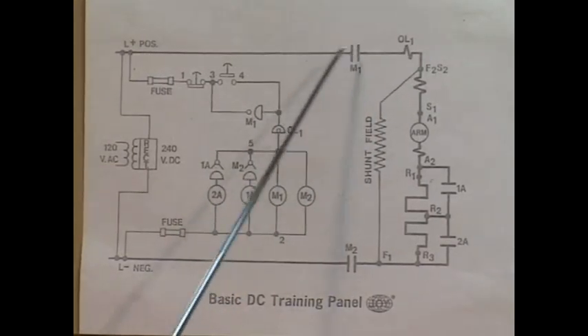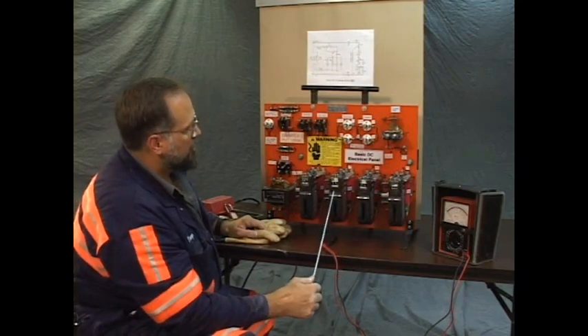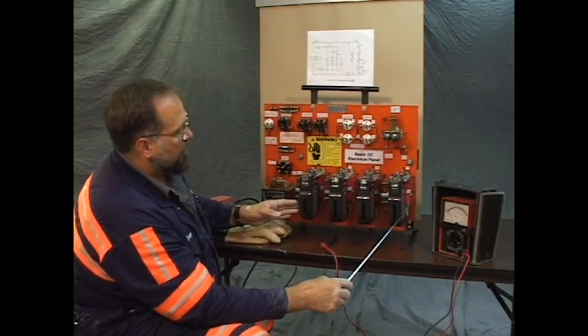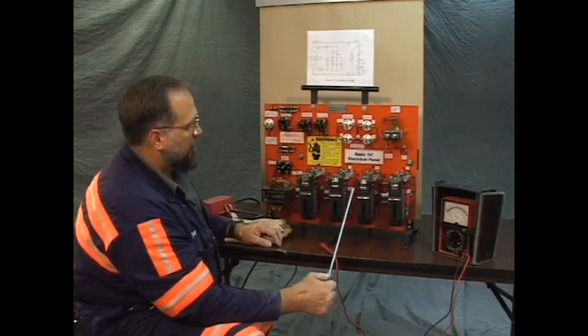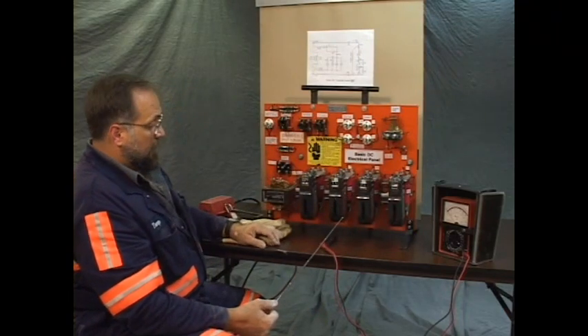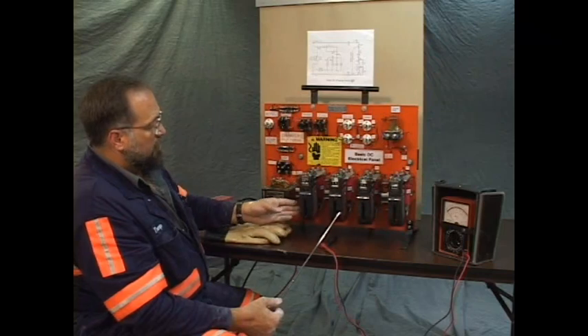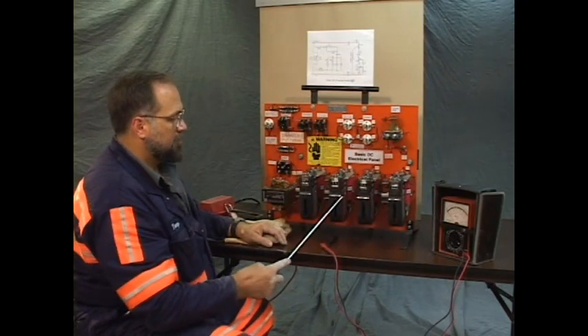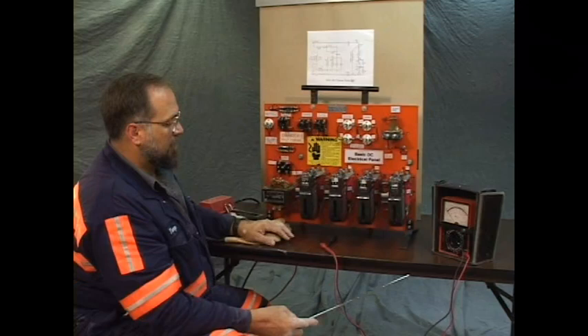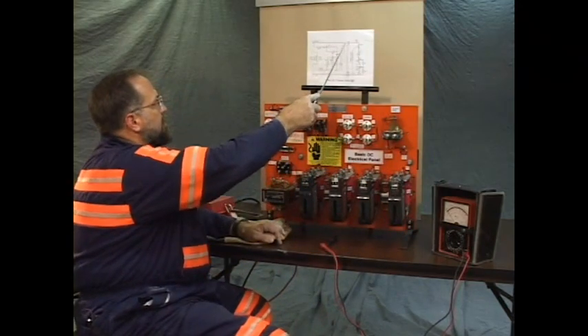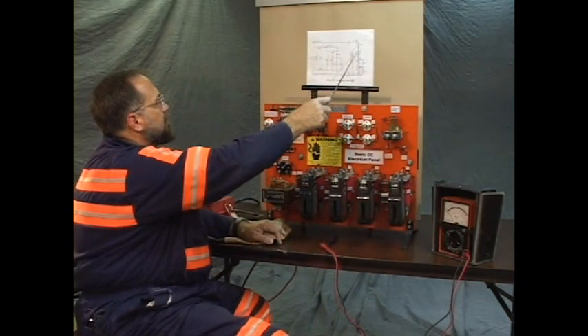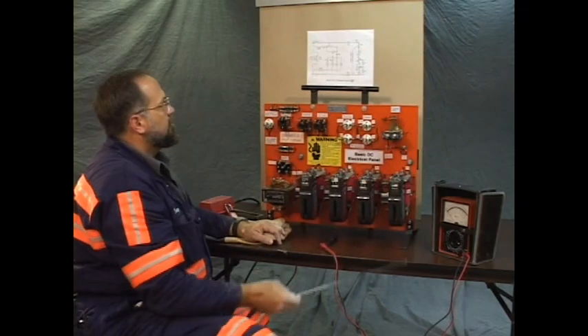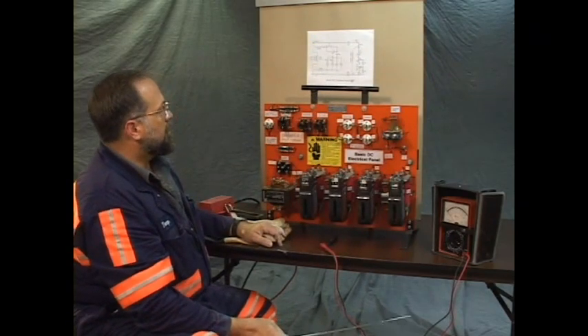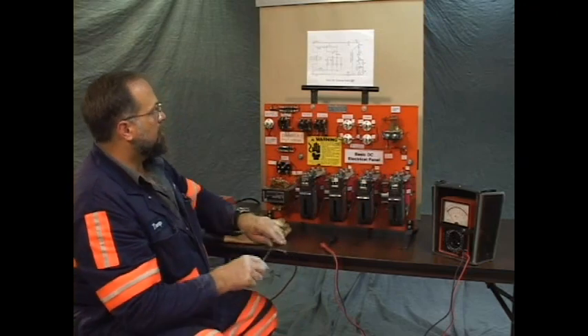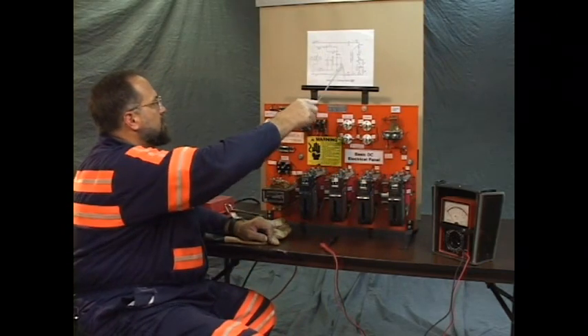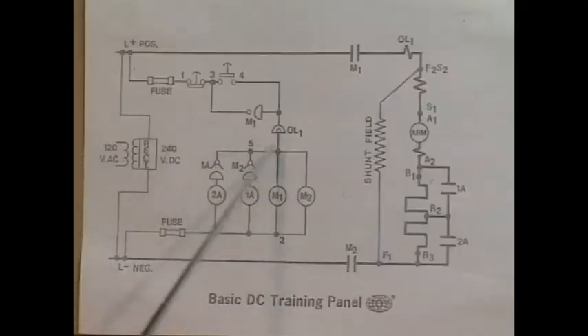This contactor's not closing. We heard 3 clicks. M1 and M2 are supposed to start simultaneously, then 1A, then 2A. But if you were observing, you'll notice M1 didn't close. M2 closed, 1A, 2A. M1 didn't close. When this doesn't close, the positive side of the rectifier is not connected to the motor. If the contactor doesn't close, it's a control problem. So we're going to check the control portion of the print, particularly with M1.